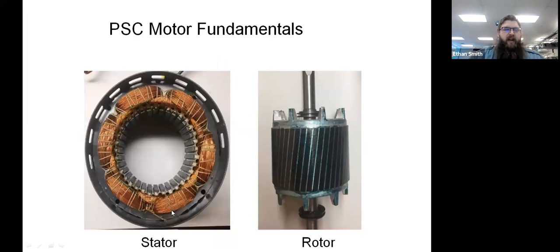There's a picture of what we're looking at there. This is the stator of that PSC motor that we were just looking at. We've got the rotor here. That's a cage style rotor. It's got different metals here: a set of bars that runs up at an angle through this rotor, and then a bunch of laminated steel plates that sandwich into the middle of those bars. The way that's designed is, as these coils energize, they induce a magnetic field in this that helps drag that rotor around. But if you look at this, we've actually got two windings here. We've got our stator, which is the big one, like right here, and we're using 1, 2, 3, 4, 5, 6 run windings in this stator. And then you see this other fine, smaller coil of wire, and that is our start winding.